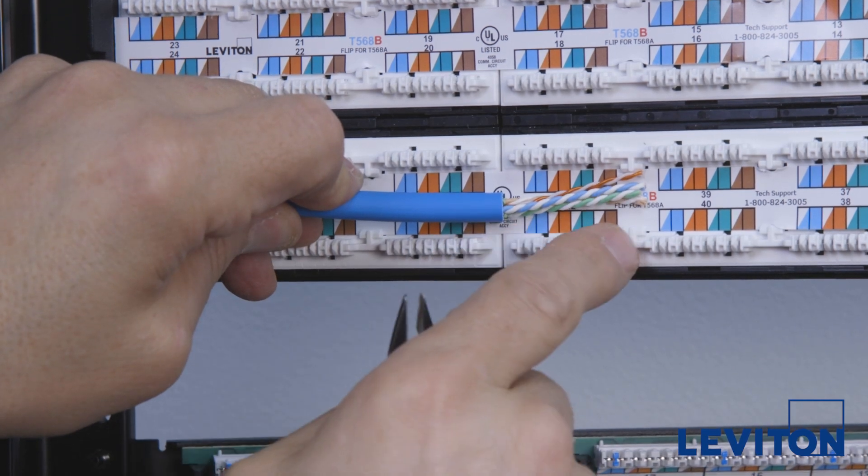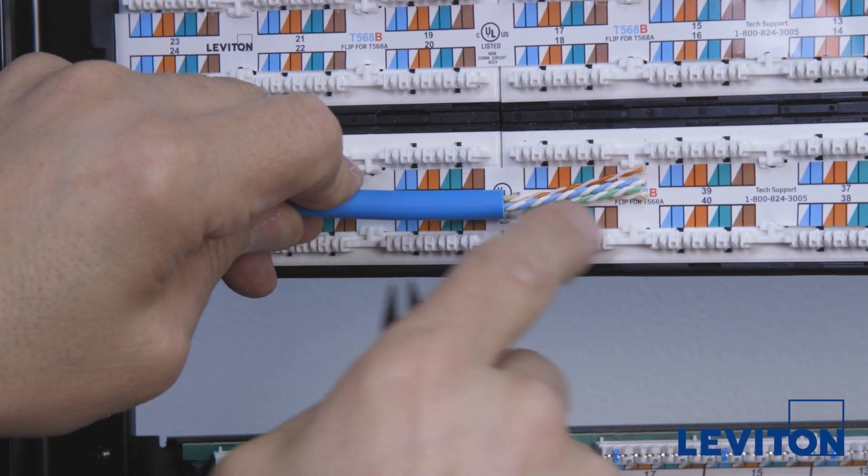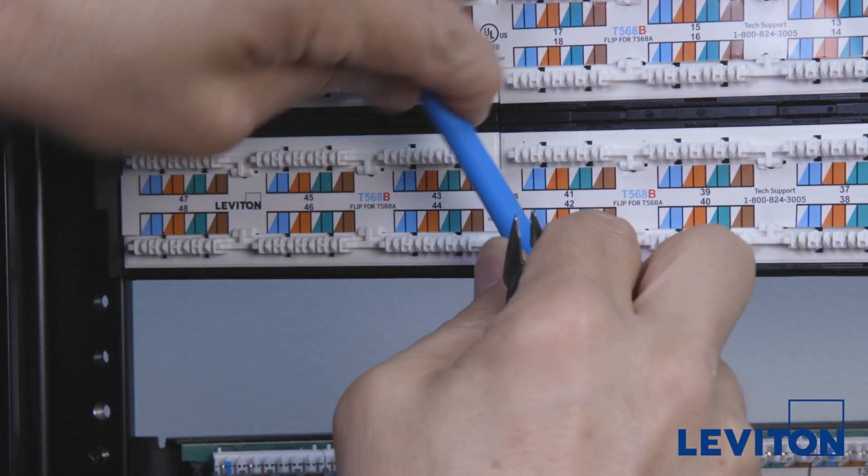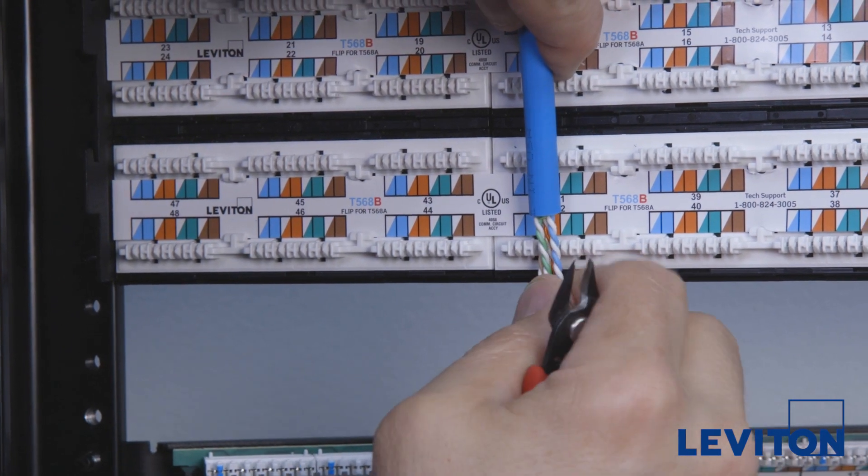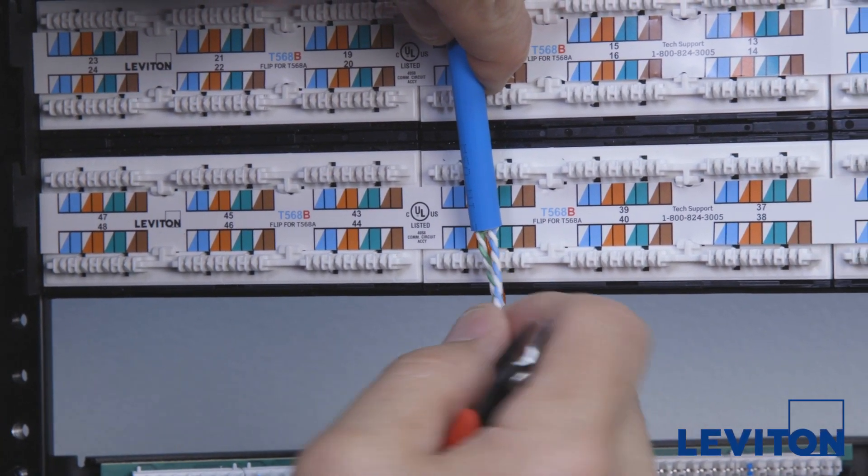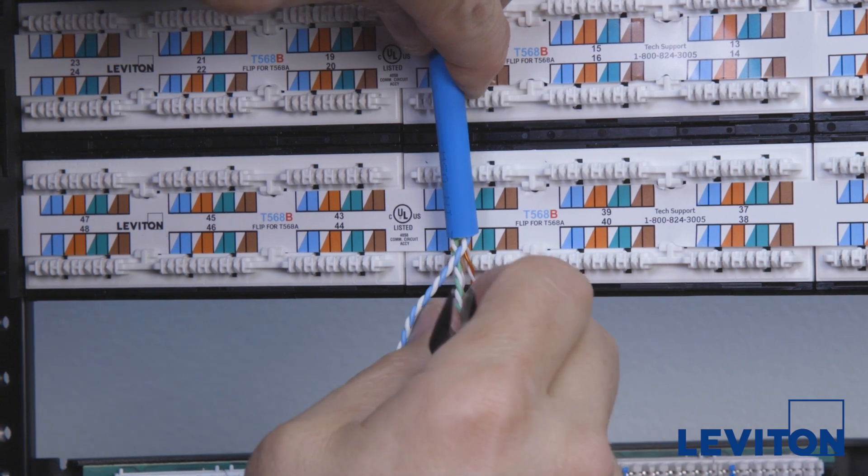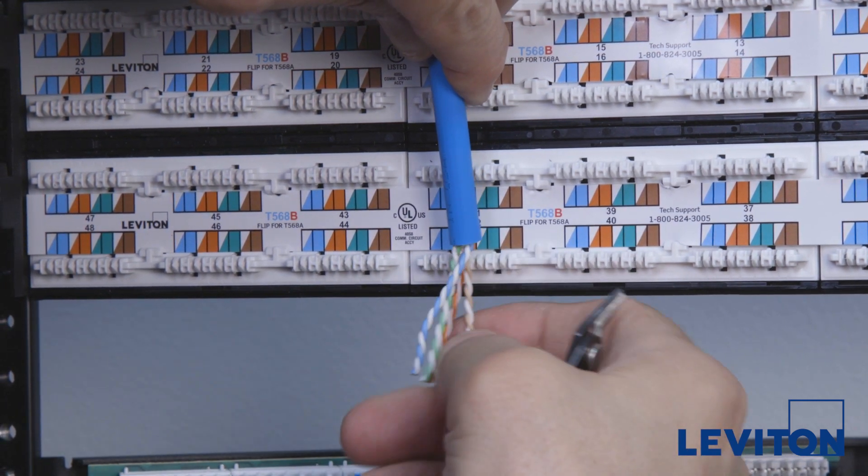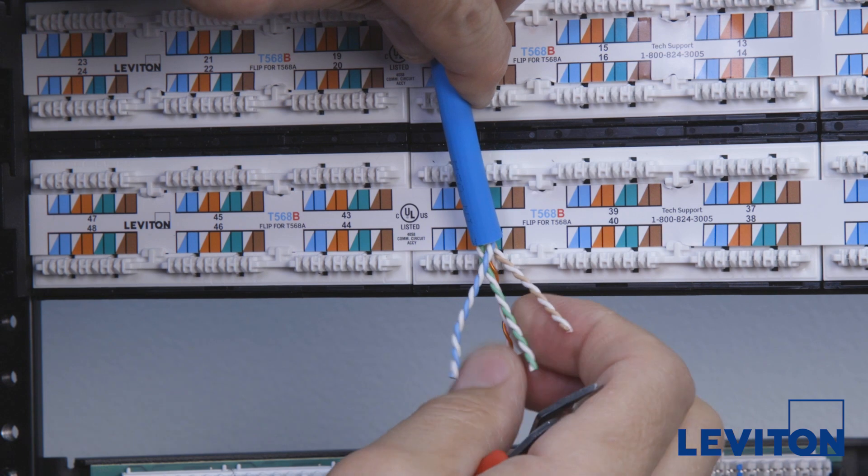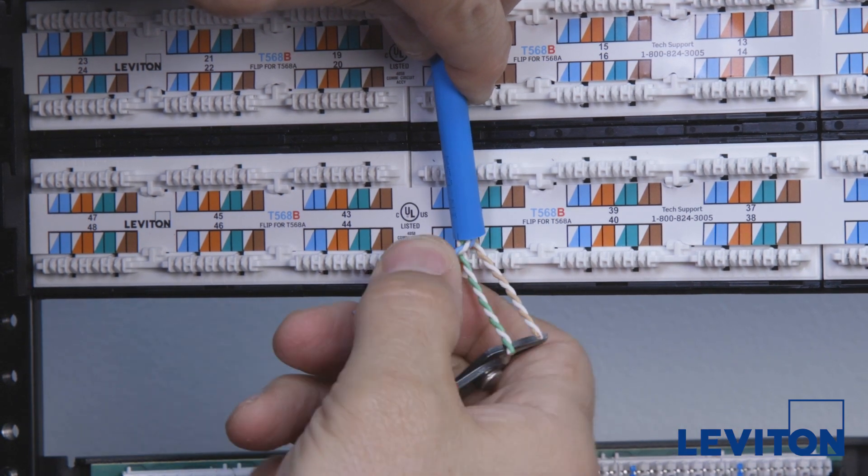A common mistake is to come into the IDCs from the side, but doing so leaves the blue pair short and the brown pair long. A better approach is to come down the center and splay the pairs out to where they are needed, as indicated by the colored marking on the IDC. This way, all of the pairs end up being an appropriate similar length.